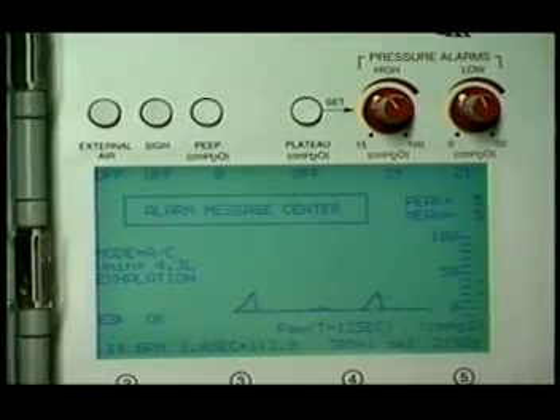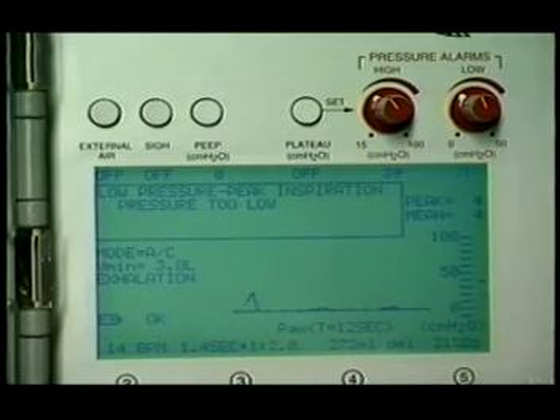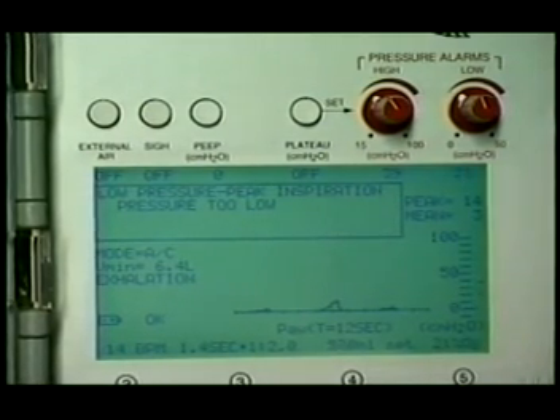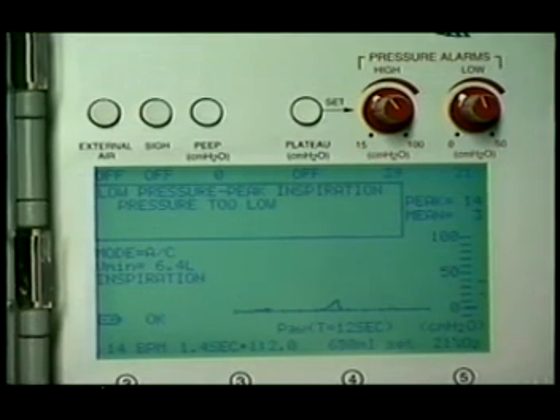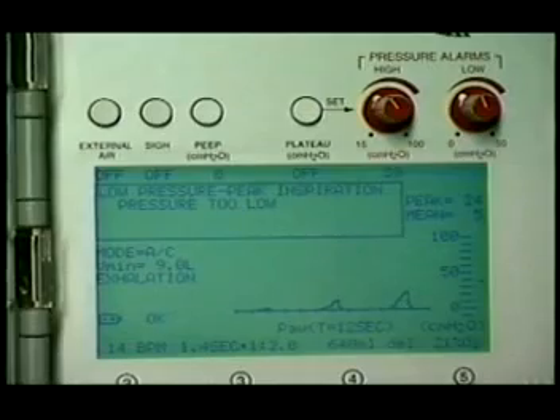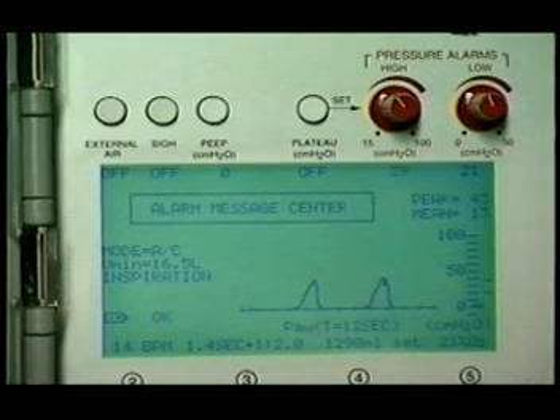If it stays below the low pressure alarm set point for 2 consecutive breaths, it will trigger the low pressure alarm. This virtually eliminates nuisance alarms by requiring 4 consecutive high pressure alarm set point violations and 2 consecutive low pressure alarm set point violations to trigger their respective alarms. You might ask, what happens if the patient coughs or exceeds the peak inspiratory pressure relief limit during 1 breath or 2 or 3 consecutive breaths? How is the patient protected?